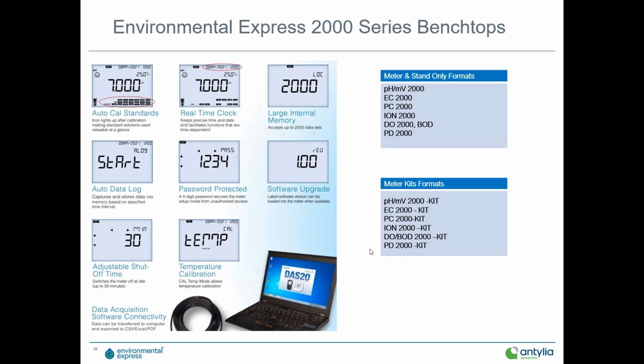Some of the upgrades on the 2000 model: AutoCal standards. It's got the real-time clock. It's got 2,000 data points. These can be downloaded easily via the complementary software and cable, and the time and date stamp for building an audit trail. It's got the auto data log, which is similar. Password protect, that's a different feature on a 2000. Software, of course, is upgradable. Adjustable time off from 1 to 30 minutes, and the temperature calibration.